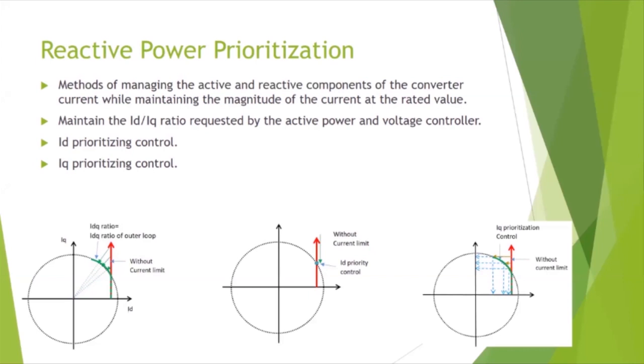So I'm showing three different approaches here. On the left, if the desired ID, IQ is on any point on this red arrow, you simply join that point to the origin and get the point of intersection between that line and the circle. Then you can bring the current to the rated value. So in other words, you maintain the ratio between the desired ID and IQ and scale down the magnitude to bring the total current to the rated value.